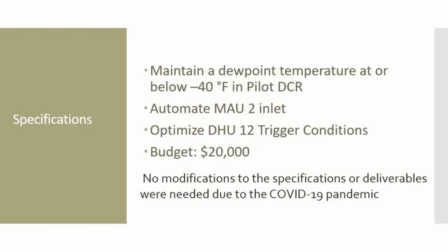The specifications of this project include maintaining a dew point temperature at or below negative 40 degrees Fahrenheit in the pilot dry clean rooms, to automate the MAU2 inlet that controls the intake of outdoor and indoor air, to optimize the DHU12 trigger conditions, and to maintain a budget under $20,000. We did not have any modifications due to the COVID-19 pandemic.